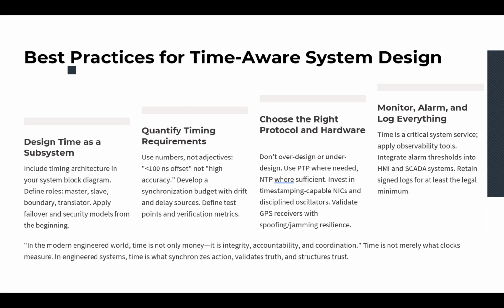So when you design a system, you have to consider time tagging and synchronization with the master clock. All these parameters and criteria define how well you did your design, and how reliable the system works. After that, for best practices, we have to choose the right protocol and hardware. Time synchronization is not a one-size-fits-all solution. If we choose the wrong protocol, which is too complex or too weak, over designed or under designed, that could cause either wasted resources or catastrophic failure.